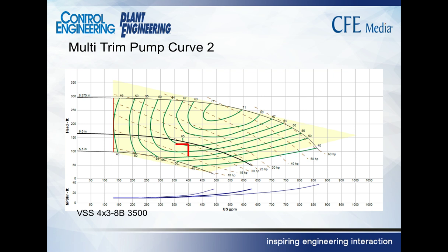There's a smaller pump. It has a 4-inch suction line and a 3-inch discharge. An 8-inch impeller runs its 2-pole, 3,500 RPM. And it has a flow rate of 400 gallons per minute and a head of 125 feet, same operating point. But notice how close to the best efficiency point this pump is operating.